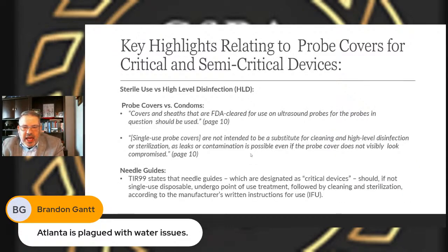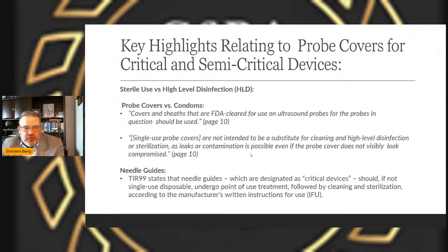Now, the key highlighted areas to cover in this are probe covers versus what they call condoms. And this is on page 10. Covers or sheaths that are FDA cleared for use in ultrasound probes should be used. In other words, if you have a probe, you should be using some type of sheath or protective cover, so that if by chance there's a break in the skin barrier, blood, an ulcer, a perforation, or a puncture, a high-level disinfected probe is not coming in contact with that blood or passing the mucous membrane barrier. And that's on page 10.